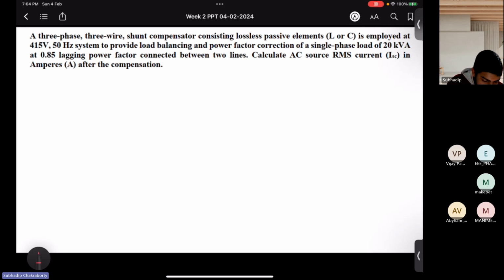So what it is telling, it is a 3-phase 3-wire system, right? And you have to provide load balancing and power factor correction. Single phase load is connected to any of the 2 lines, of 20 kVA at 0.85 power factor lagging. So net loading is 20 kVA at 0.85 power factor lag. So what is the active power?